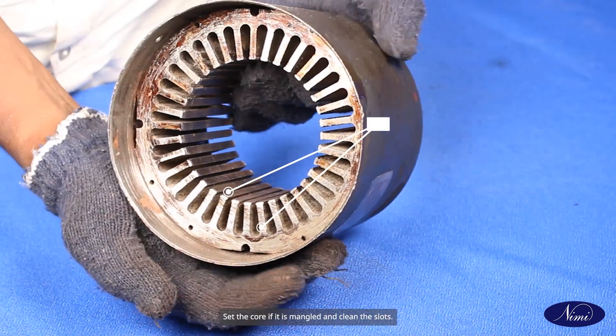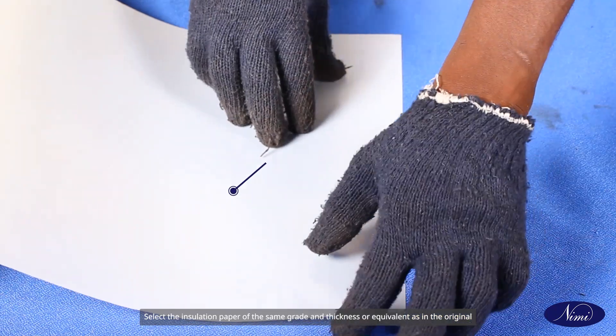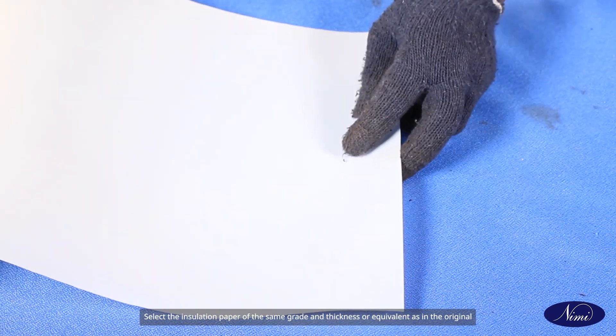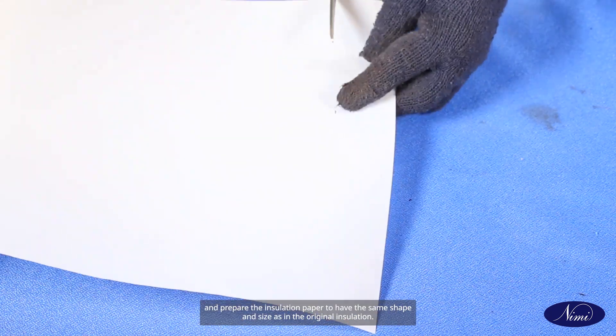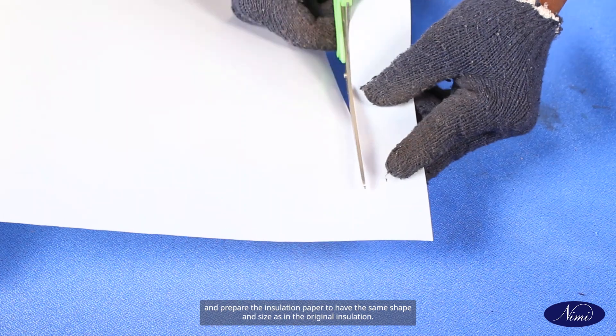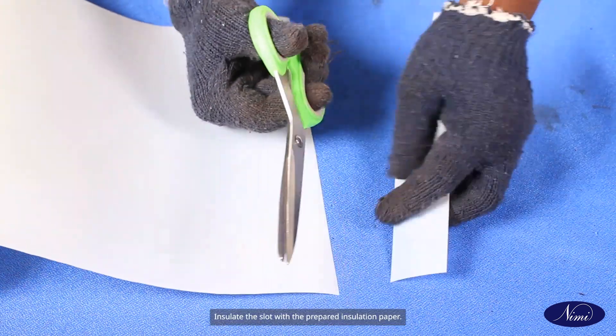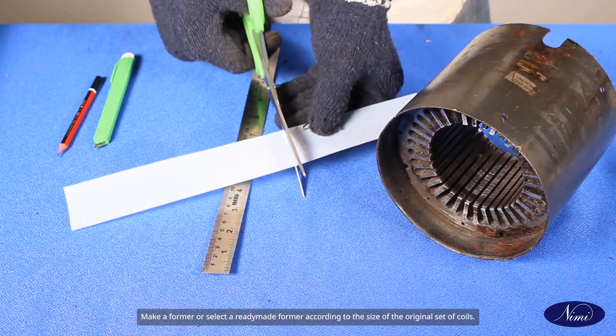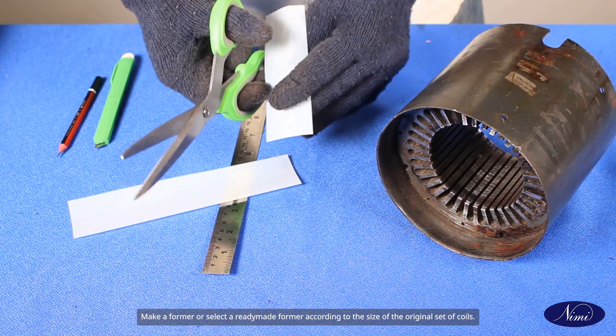Select the insulation paper of the same grade and thickness or equivalent as in the original and prepare the insulation paper to have the same shape and size as in the original insulation. Insulate the slot with the prepared insulation paper.